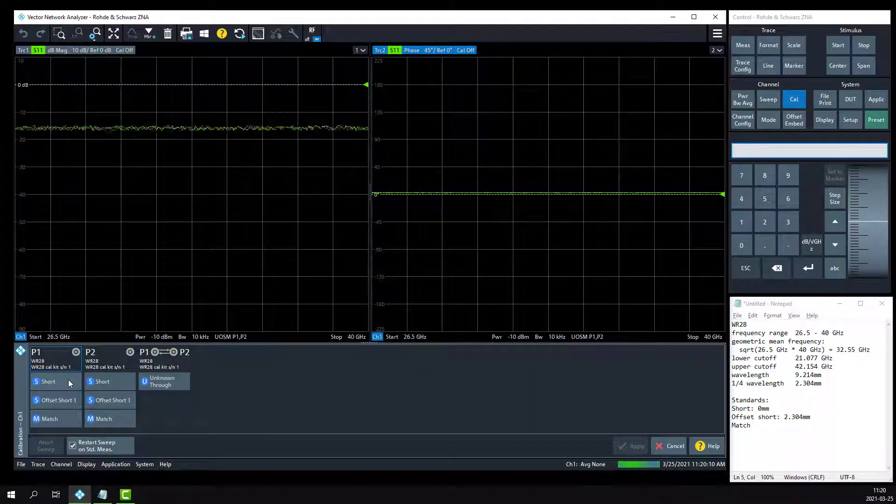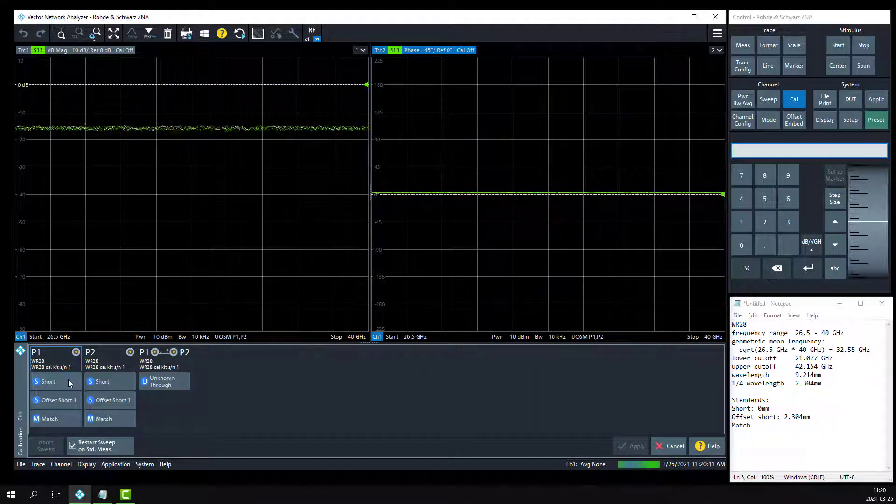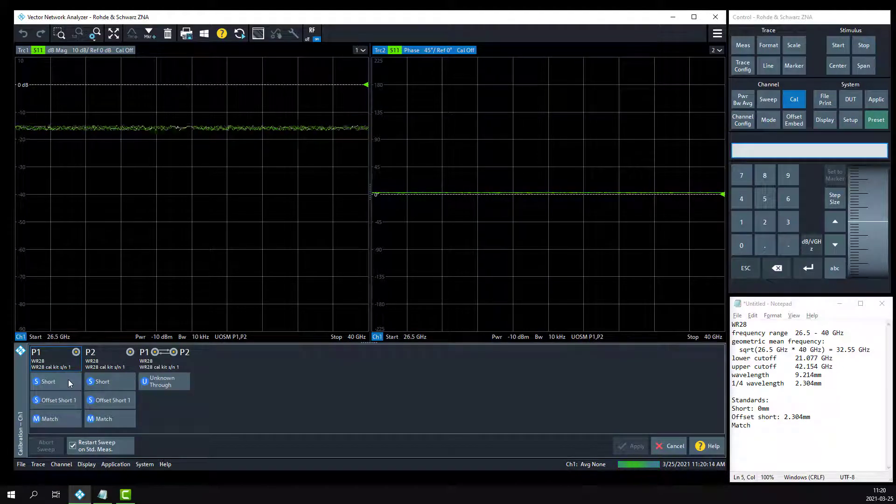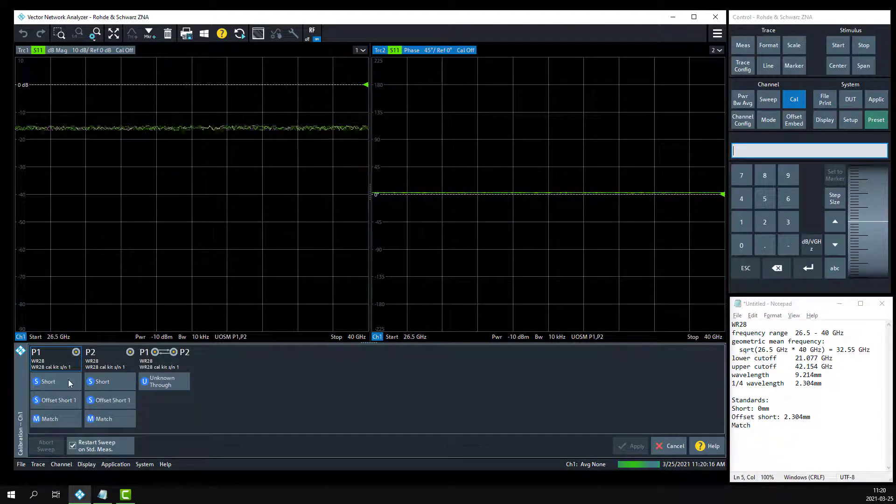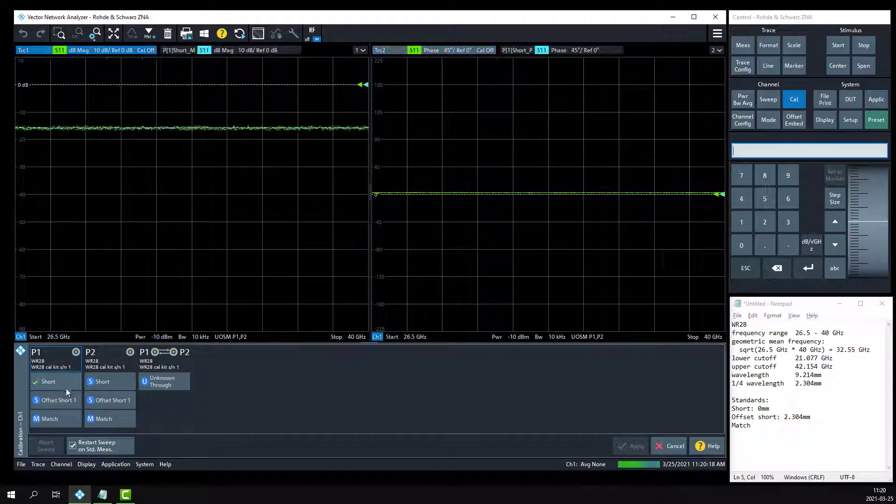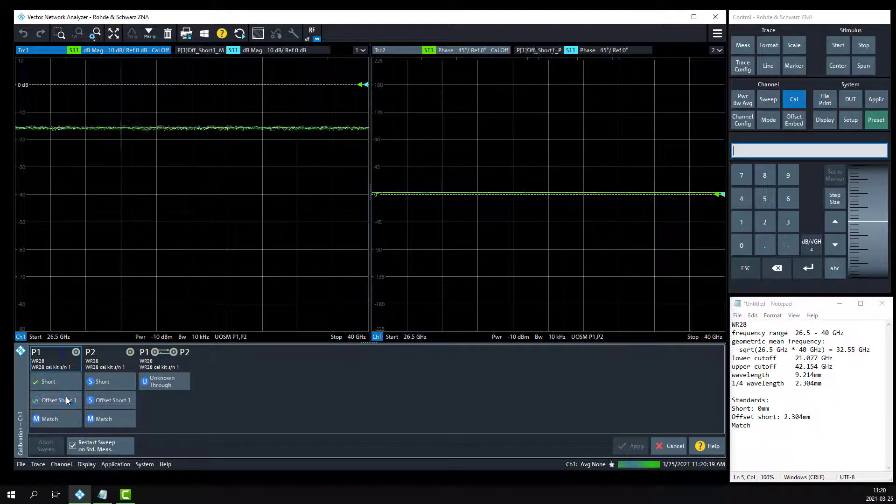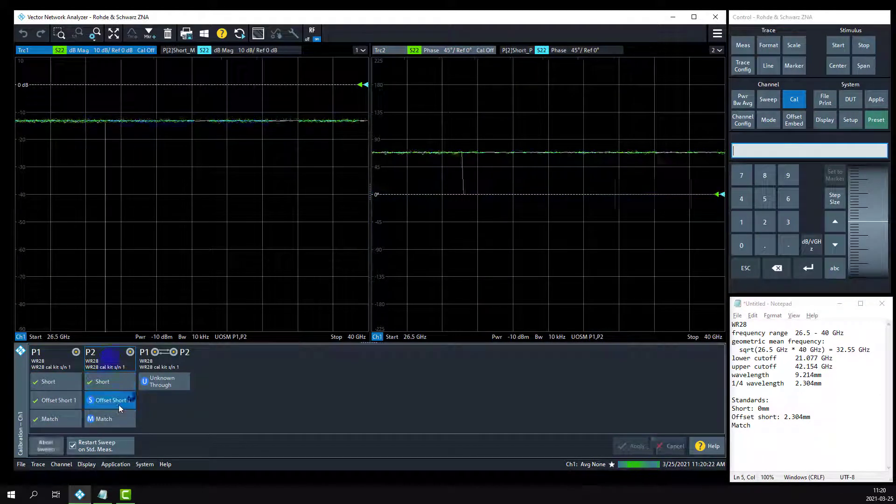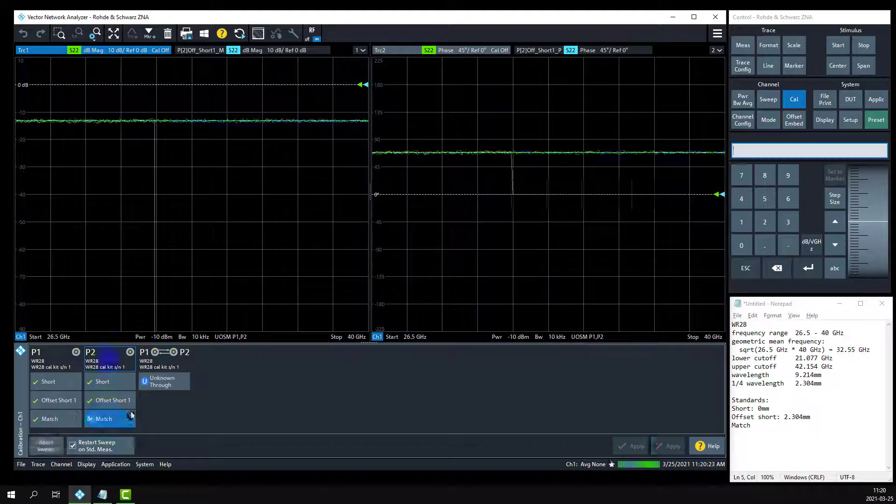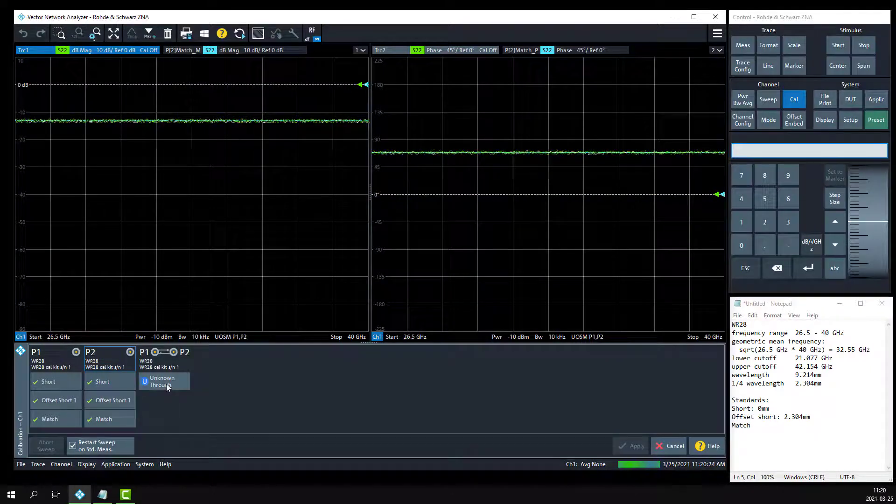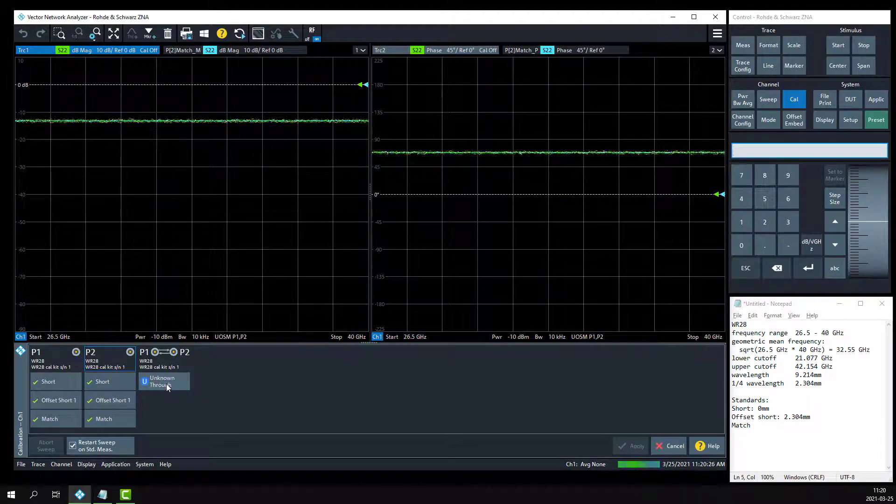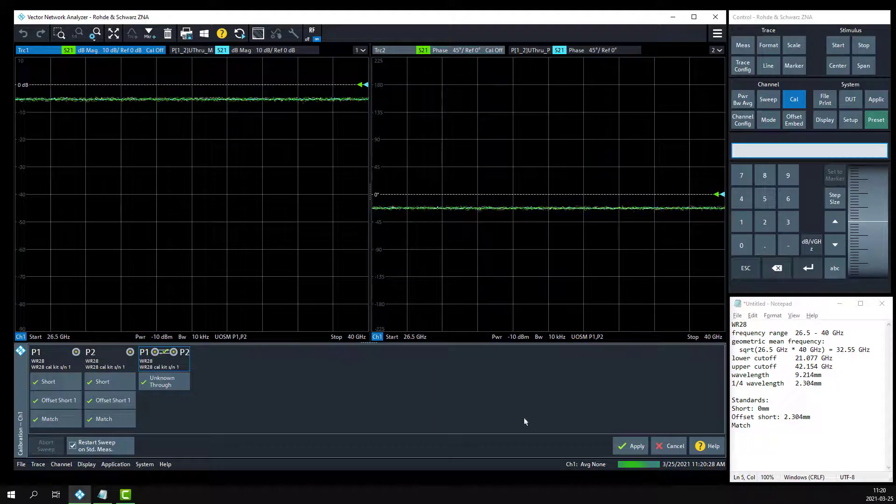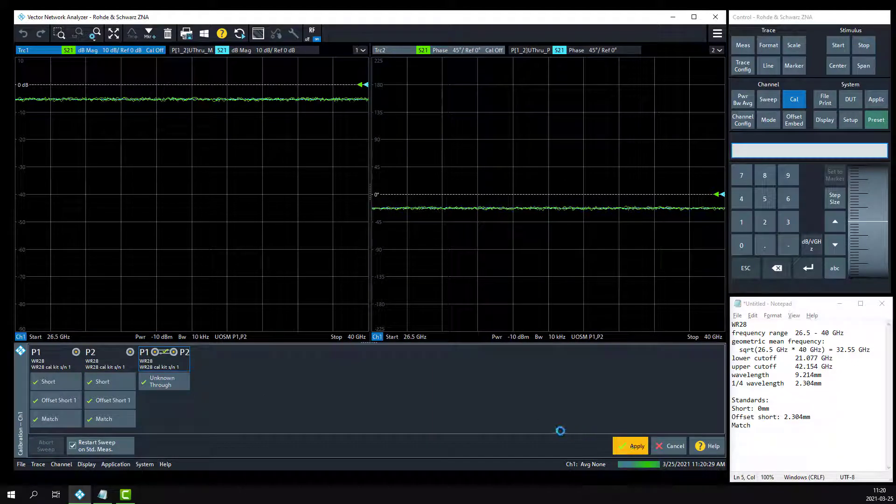And then we will sequentially connect the standards that we defined in our calibration kit to port 1 and 2. We can do this in any order. And finally, we'll connect port 1 and port 2 together. Click the apply button when we're done with calibration.